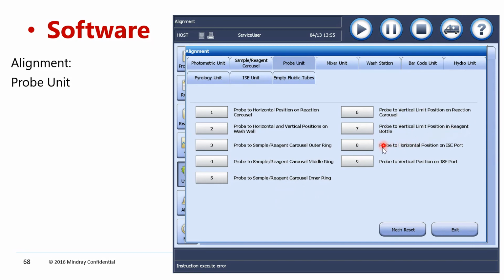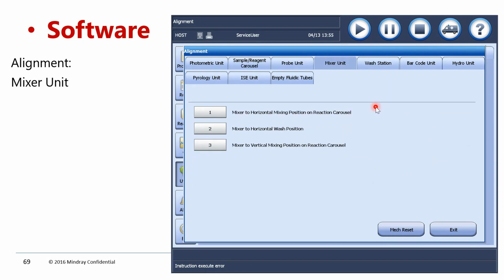Okay, so probe to horizontal position to ISE. This is for ISE position, up and rotation, as well as vertical. And mixer, so the mixer has a horizontal position and wash station position, right? Cuvette position as well as wash position, and there is a vertical height up to which it is not supposed to touch the bottom of the cuvette. So that is why it is important. Vertical mixing, vertical position adjustment is also very much important.